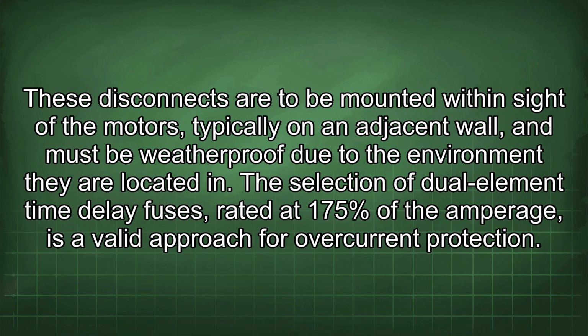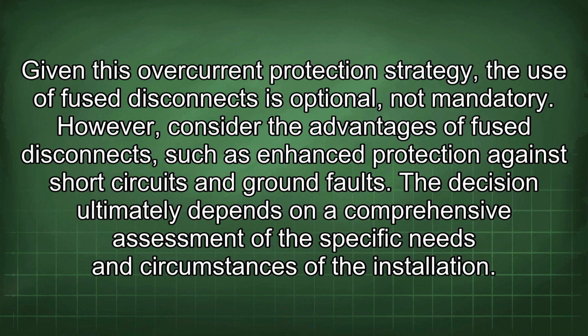The selection of dual-element time delay fuses, rated at 175% of the amperage, is a valid approach for overcurrent protection. Given this overcurrent protection strategy, the use of fused disconnects is optional, not mandatory. However, consider the advantages of fused disconnects such as enhanced protection against short circuits and ground faults. The decision ultimately depends on a comprehensive assessment of the specific needs and circumstances of the installation.